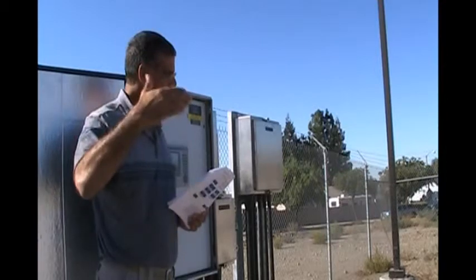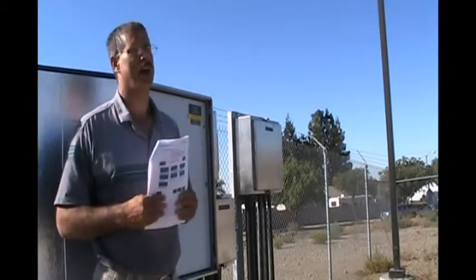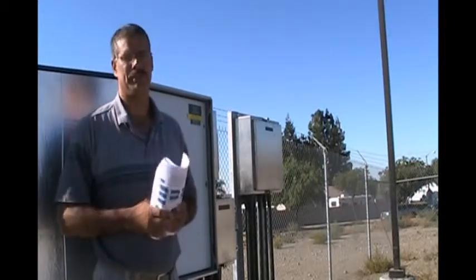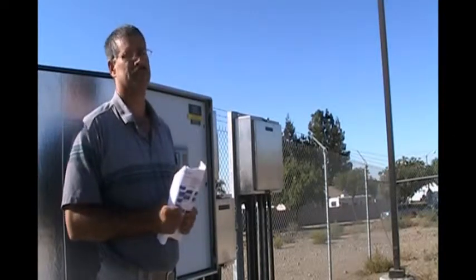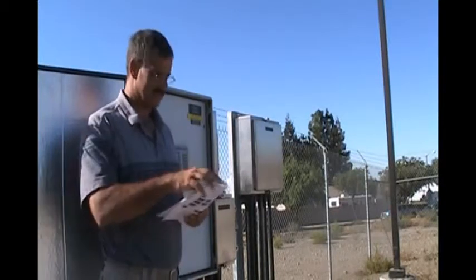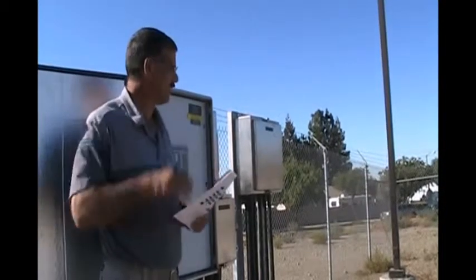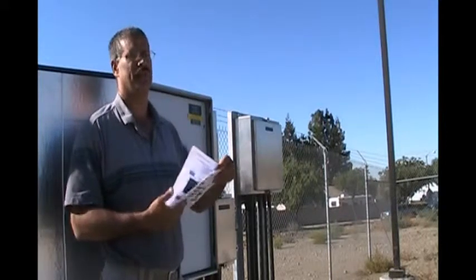If you set that above 60, what will happen is the valve will shut off, but the PLC won't know about it because it doesn't think there's an alarm condition, and the valve won't respond according to the PLC command, so you'll get a valve failure alarm. That kind of threw them off on Orchard Street at first because they couldn't figure, well, we don't have a valve failure alarm. The valve closed because it had low pressure, but that was set above what the software thinks is a low pressure. So if you need that 60 changed, then you should do that and not set the valve above it. Have that software be what enacts first, so that it has a chance to shut the valve off before the valve goes into its mechanical override.